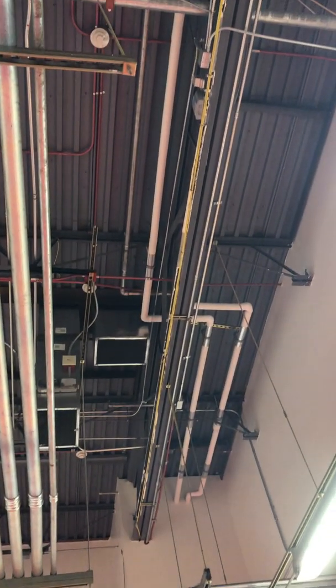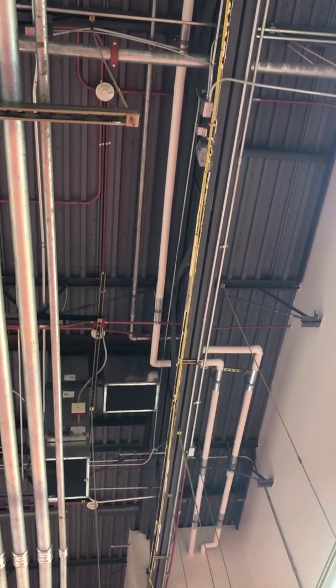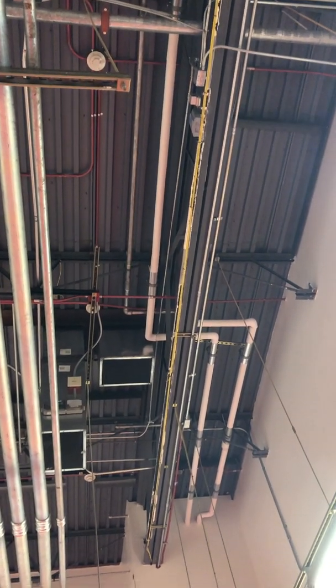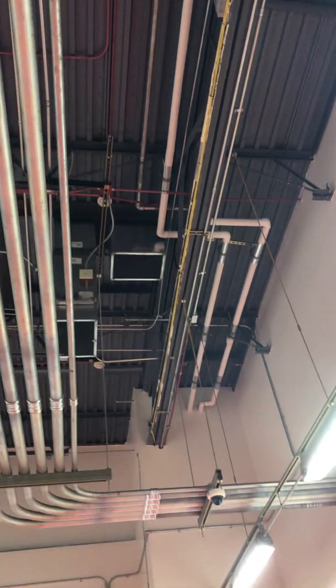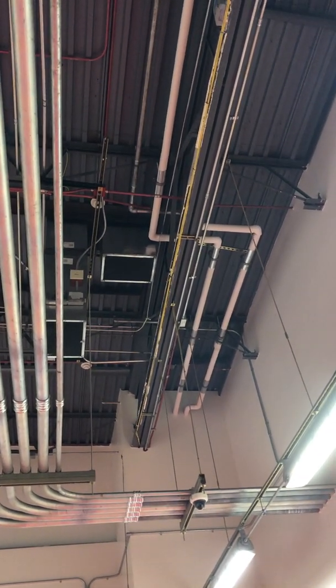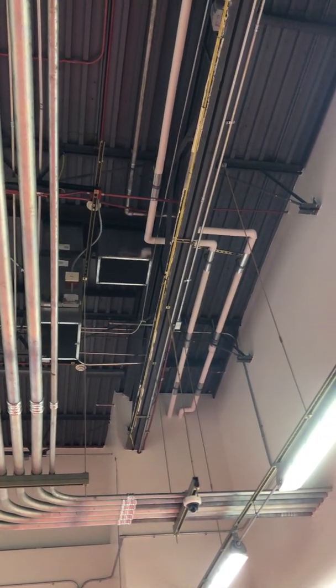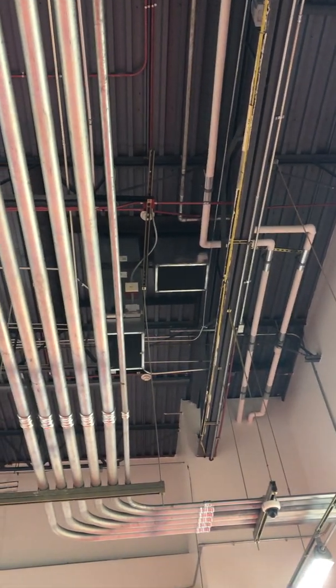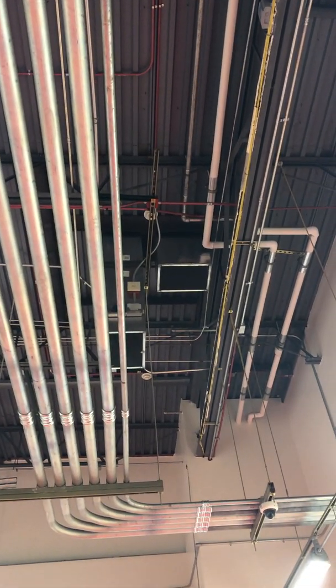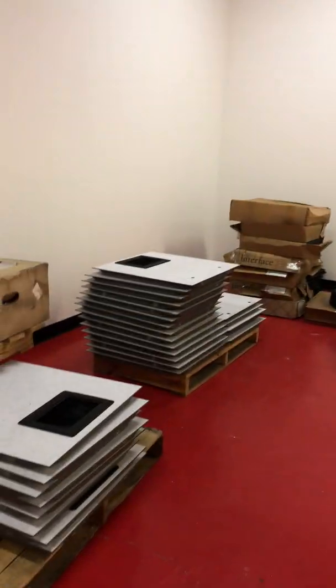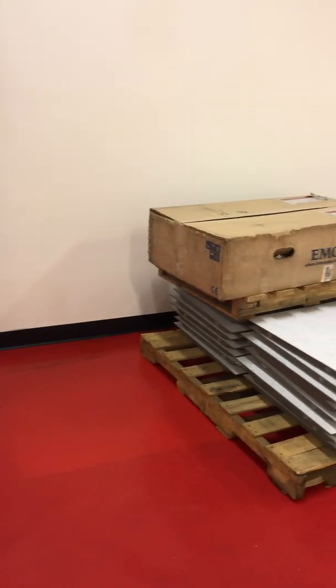Appreciate that. So, as with battery room A, battery room B, for code compliance, we'll need a second supplemental exhaust blower — it's a fairly small undertaking — and a second rooftop package unit to accommodate the additional heat load that the other batteries will represent. So the first string, where the concrete batch wasn't the greatest, went along that wall and then down to there. We blew the curb out and resealed the floor.